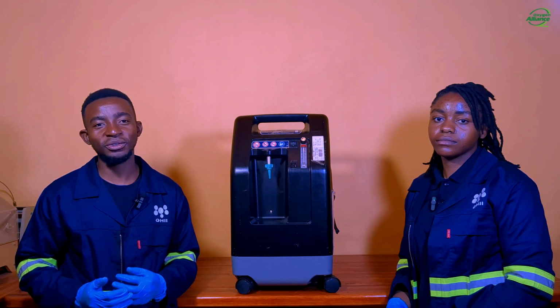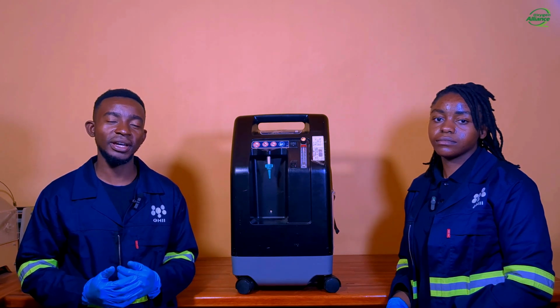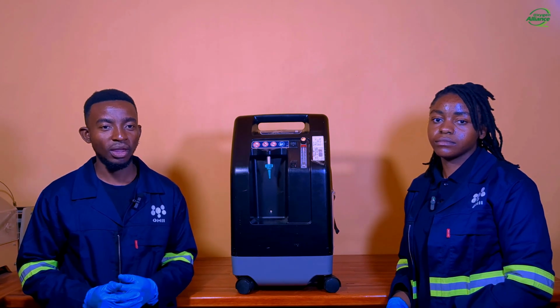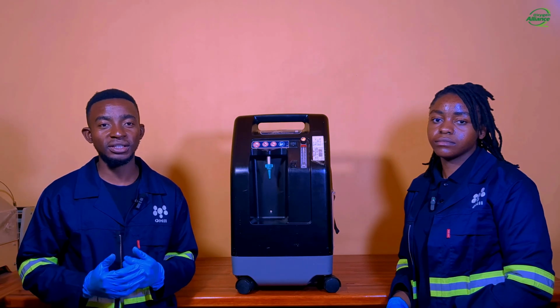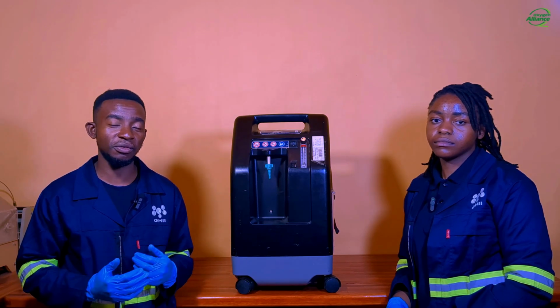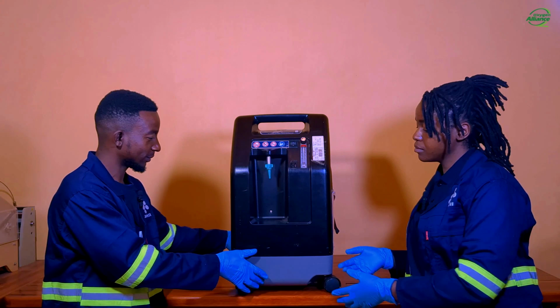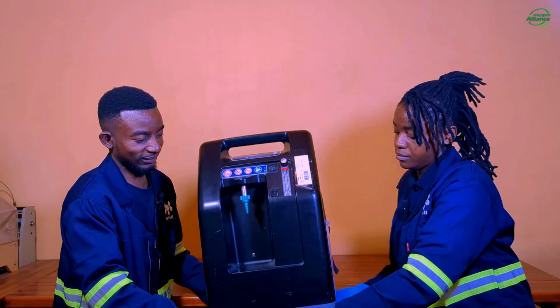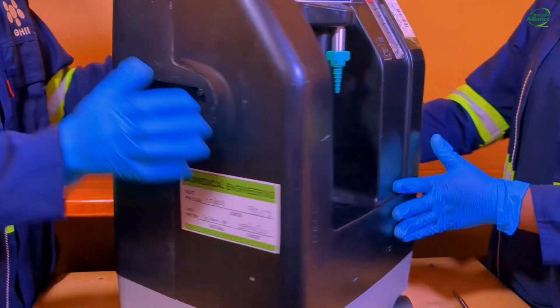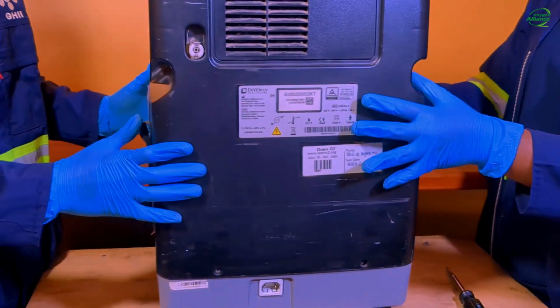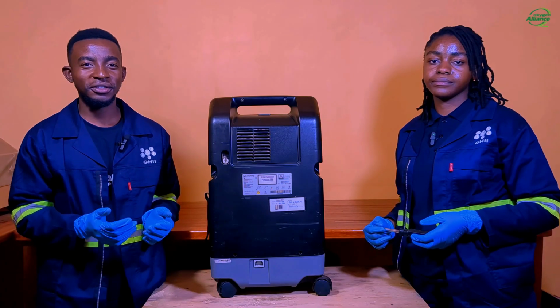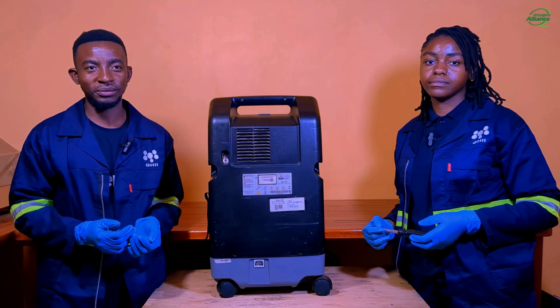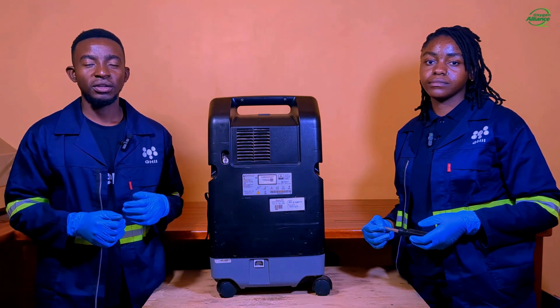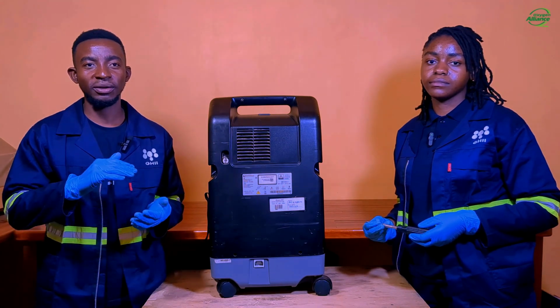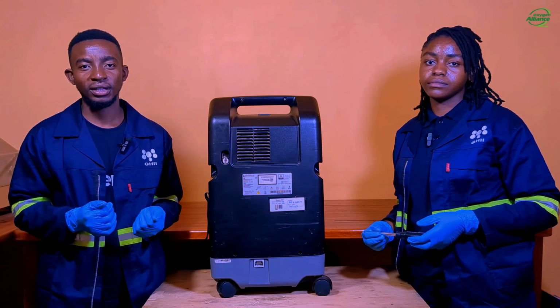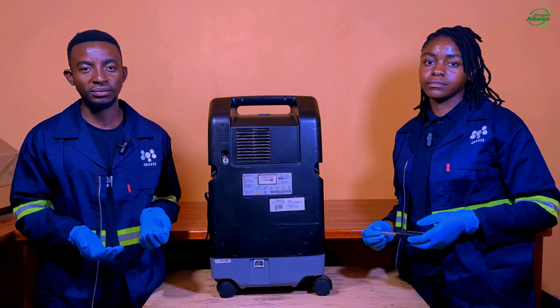Having looked at the external parts of the oxygen concentrator, now let us look at the internal parts. So in order to have access to the internal parts of the concentrator, we need to remove all the covers. Firstly, I'll start by removing the filter door. So, to remove the filter door, you need to press it downwards while pulling outwards. And I am going to demonstrate.